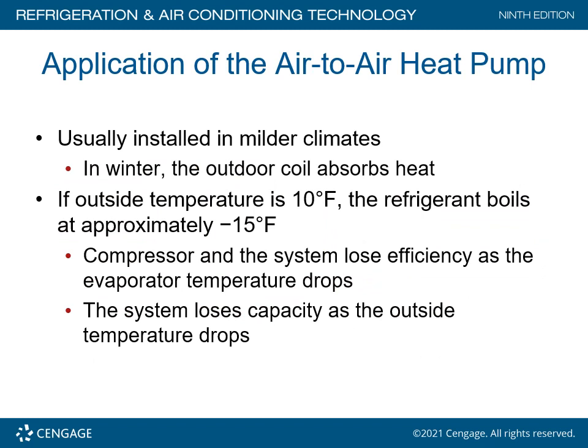The application of air-to-air heat pumps: usually installed in milder climates. They're very popular here in Southern California. They're extremely popular in Arizona. In the winter, the outdoor coil absorbs heat. If the outside temperature is 10 degrees Fahrenheit, the refrigerant boils at approximately minus 15 degrees.